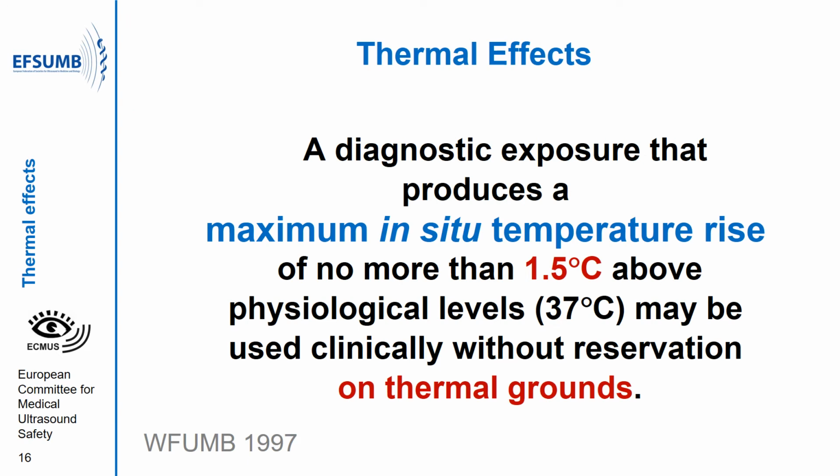The World Federation of Ultrasound in Medicine and Biology published its safety statement in 1997, stating, "A diagnostic exposure that produces a maximum in situ temperature rise of no more than 1.5 degrees centigrade above physiological levels may be used clinically without reservation on thermal grounds."